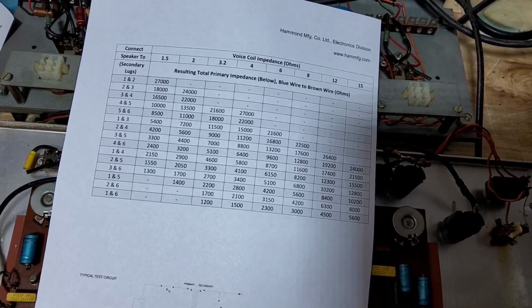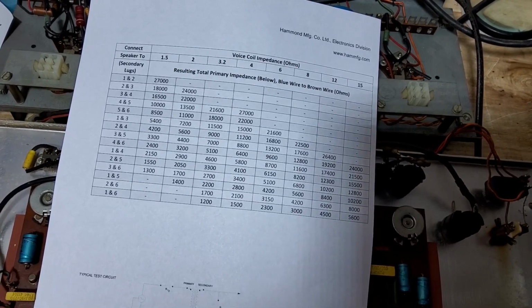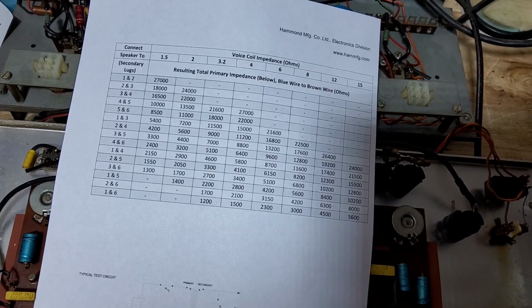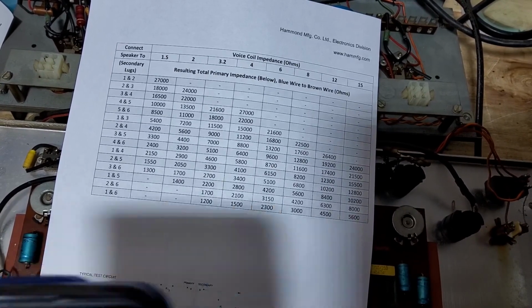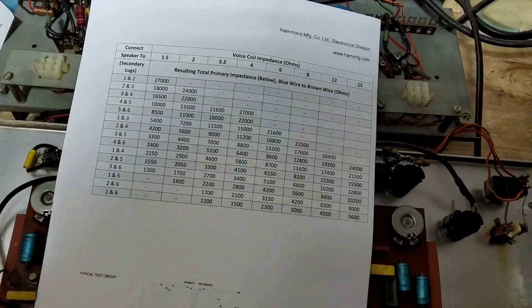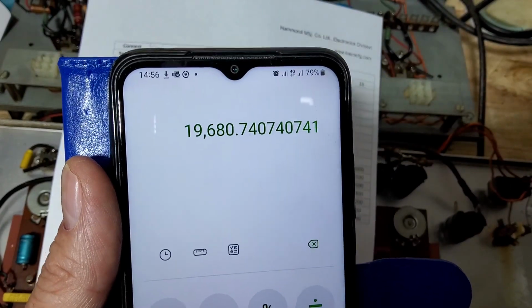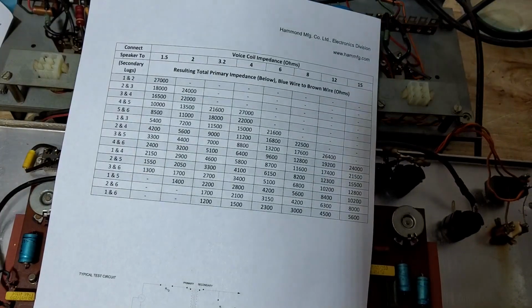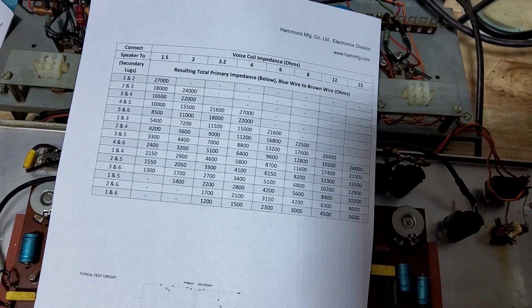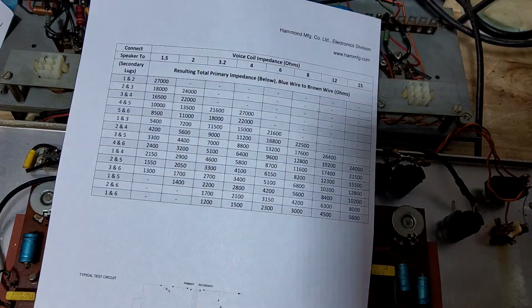So 326, if we multiply that by itself, that gives 106,000. If we divide that by 5.4, we're up to 19k as a primary there, 19.5k plus. So we're going to be somewhere between 17 and 19 more than likely, knowing what voltage we've got.